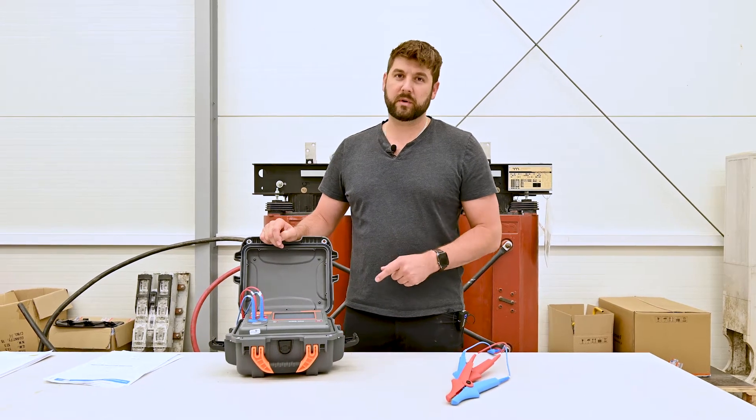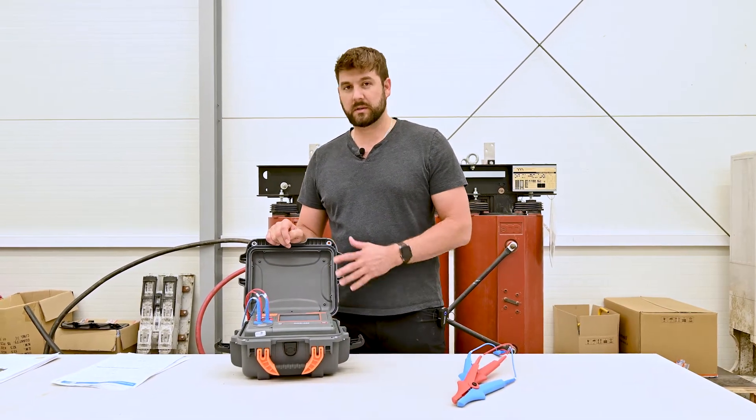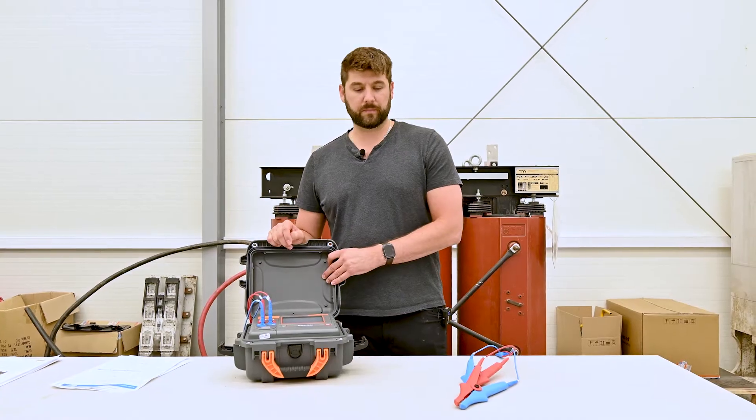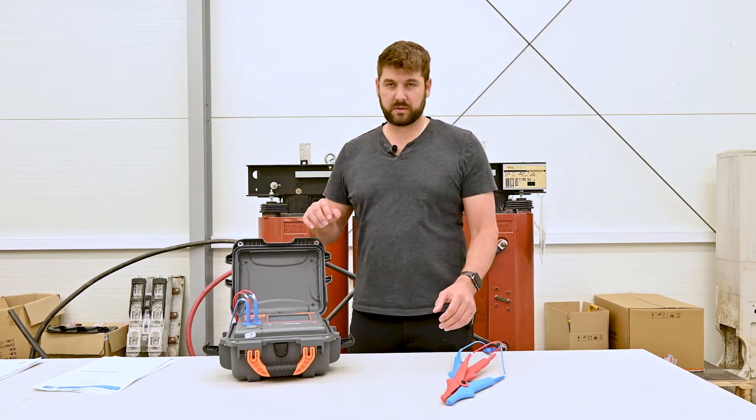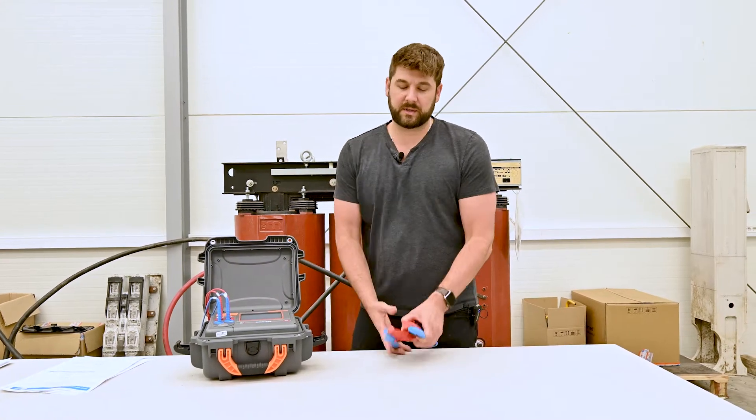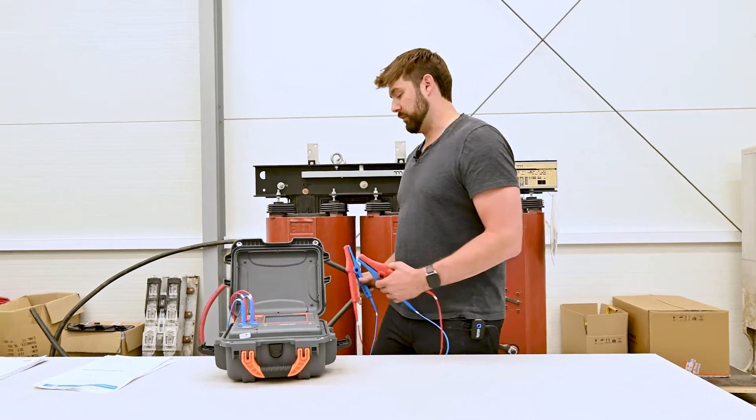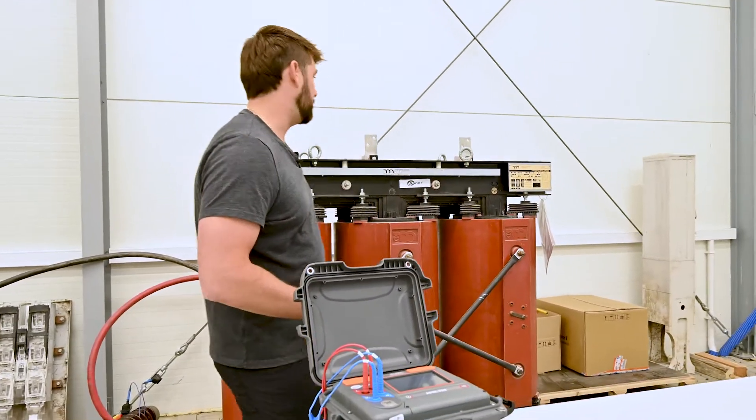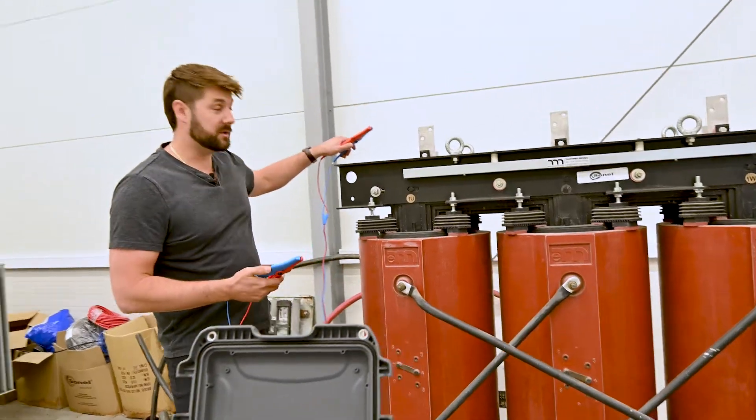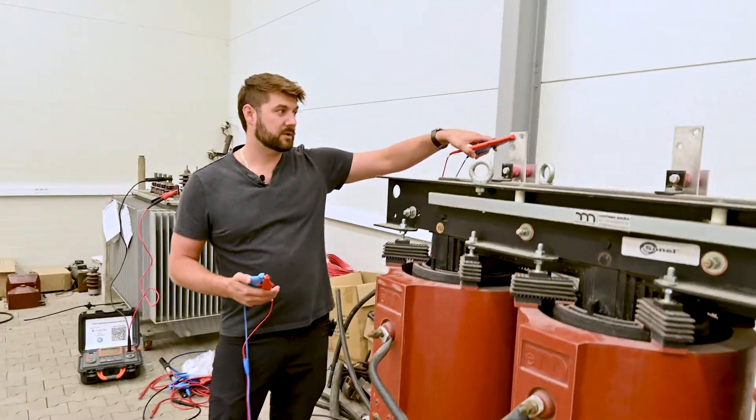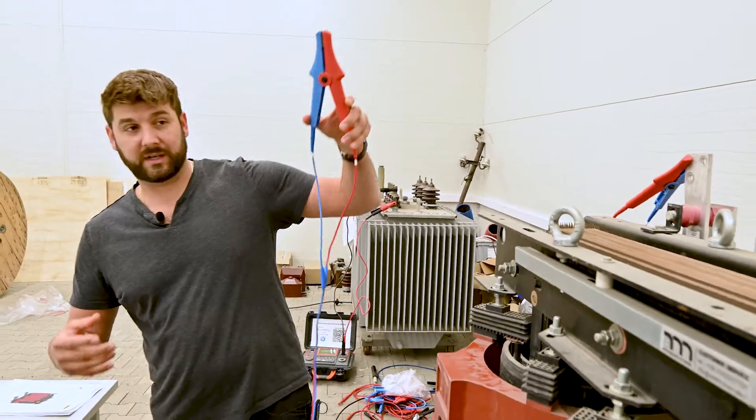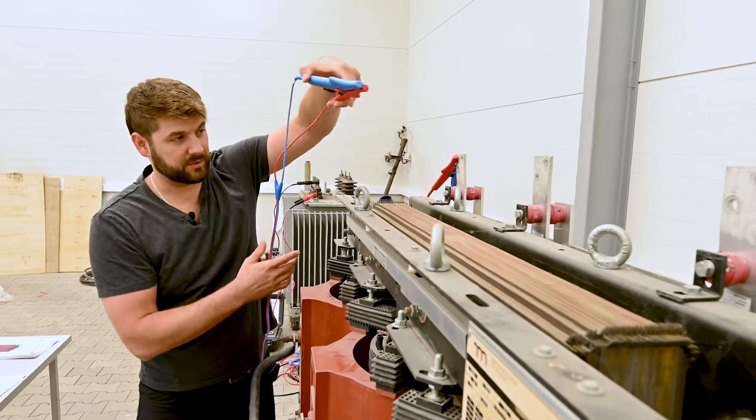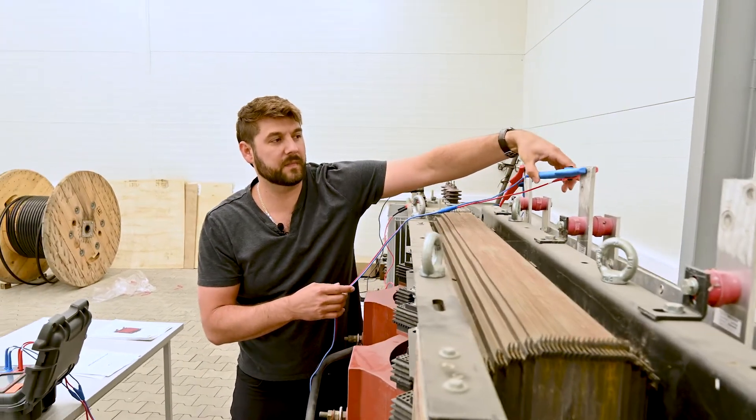Alright, so we're going to use our MMR650, which is a 10 amp micro-ohmmeter equipped to handle inductive test objects like a transformer winding. The first thing we have to do is go to the low side of the transformer, which usually has the big conductors you see here.